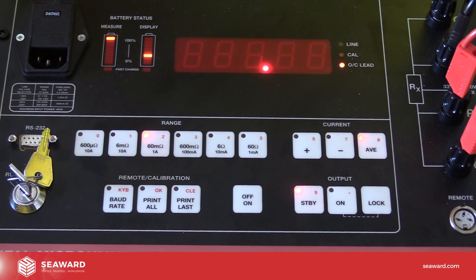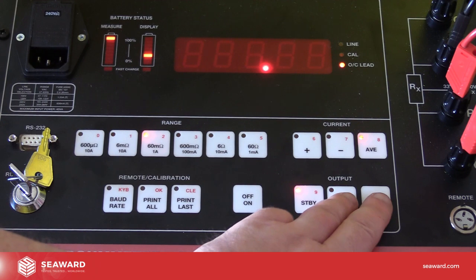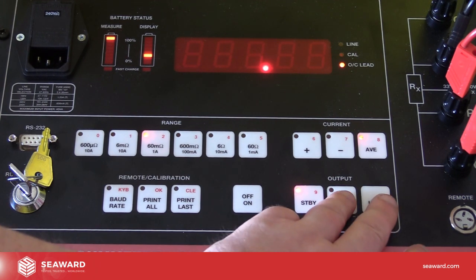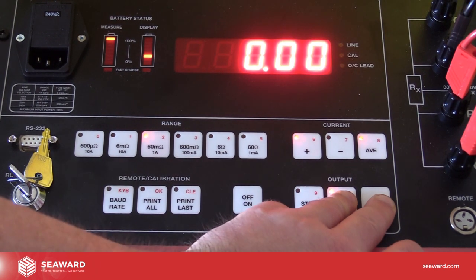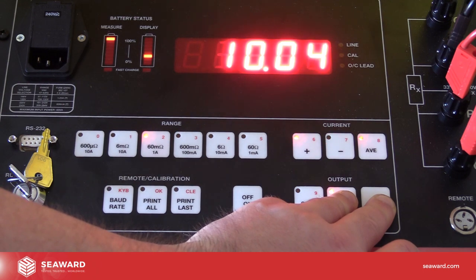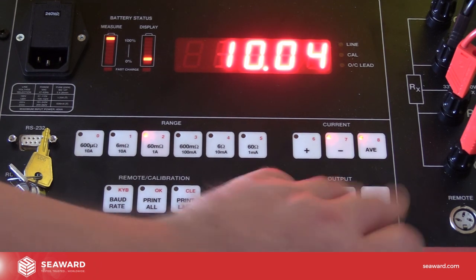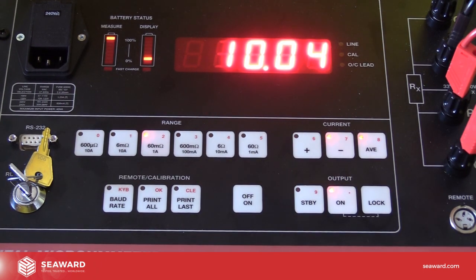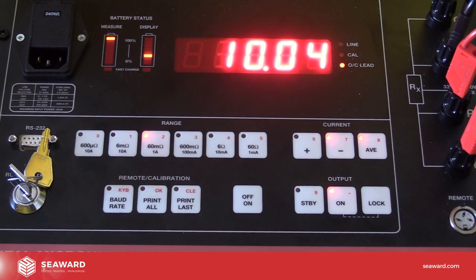So, same as before, I'm going to set this to continuously measure, so I'm going to press and hold the on and lock buttons. And you can see it's now continuously measuring. And again, we have a more optimal reading of 10.04 milliohms, giving me a much greater resolution of measurement.